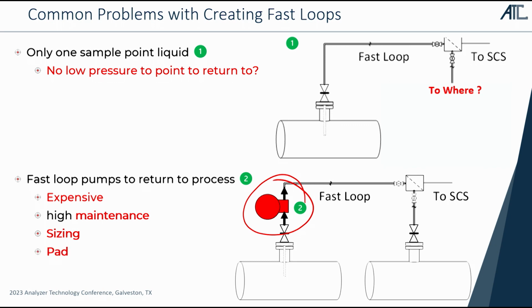And then we also say, well, it becomes this little bit of an engineering avalanche. We're going to put in a pump. Well, where are we going to put the pump? Well, we're going to pour a pad for it. Is there electricity where we're going to put the pump? No, we're going to actually do some civil. We're going to run electricity over there. Well, how are we going to know if the pump's overheating? Oh, we're going to put a temperature sensor in, and then we're going to bring that data back to see if the pump's overheating. What are we going to do if the pump fails? Oh, we'll do it twice. We'll put redundant ones in. And so we get into this little avalanche of costs and complexities in our analyzer installations.